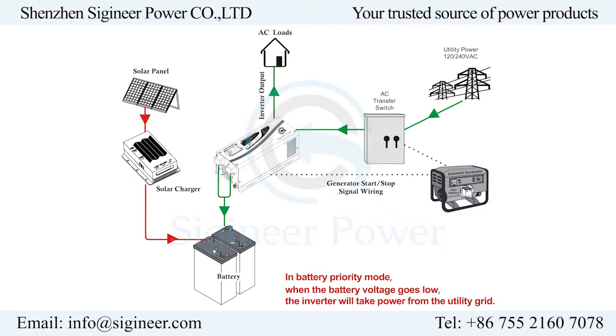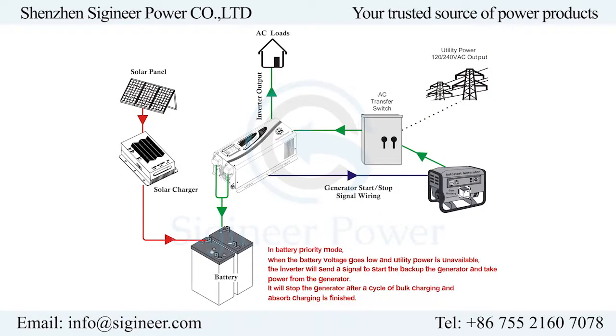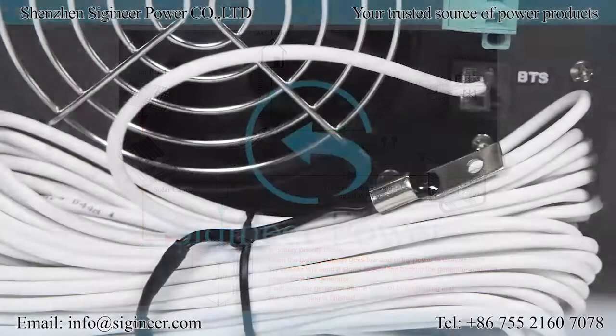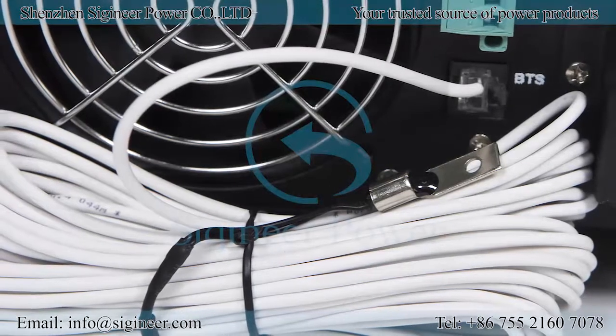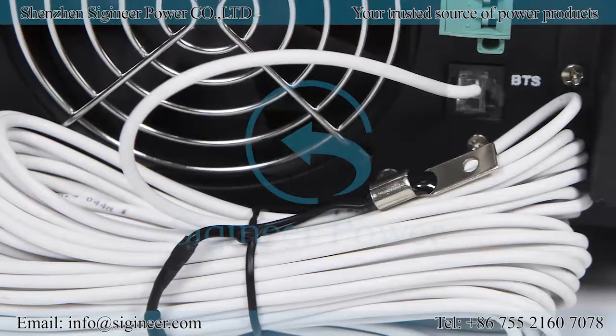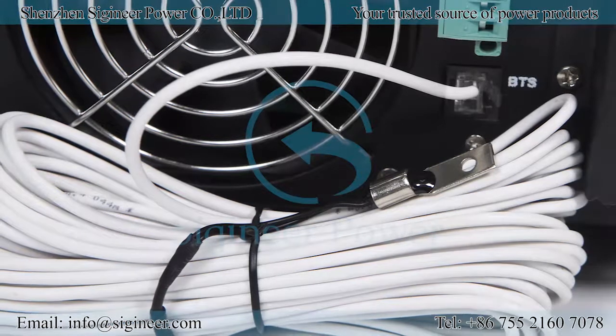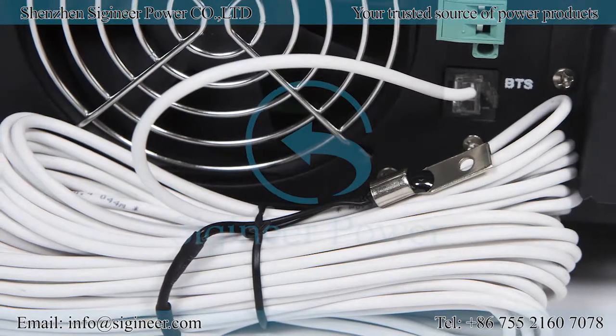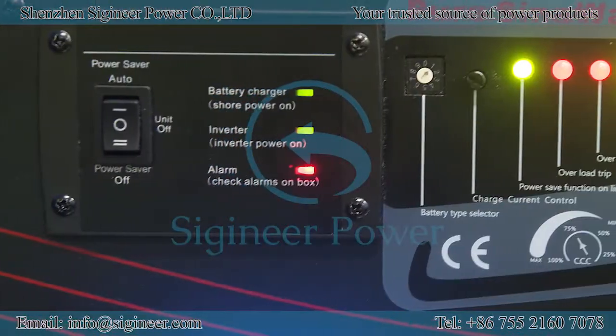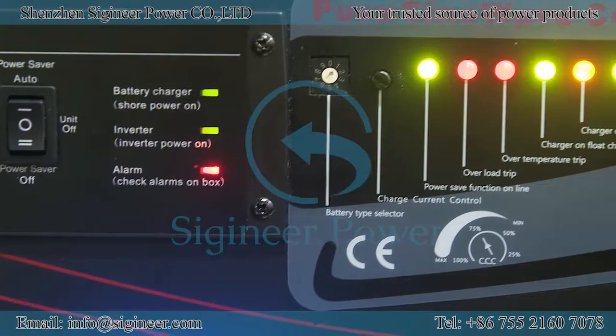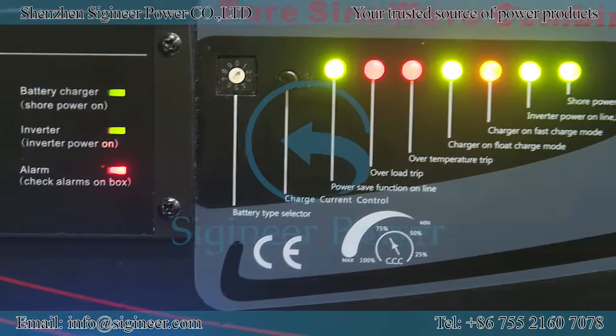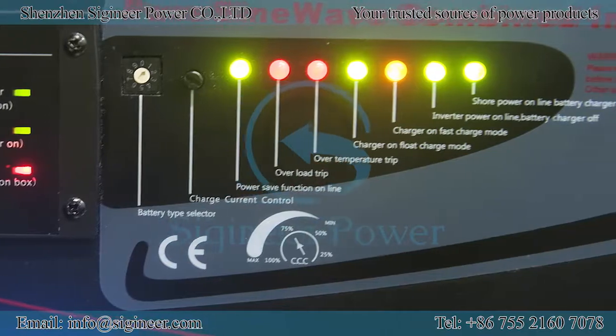The auto generator start allows standby generator to be started by the inverter and kick in when the battery voltage drops low enough to alarm. Both are great features for renewable energy power systems. An optional battery temperature sensor can be connected to monitor battery bank temperature and precisely adjust charging voltage to prolong battery life. On the top cover of the inverter, there are 3 positions: on and off power switch, battery type selector dial, and LED indicators.